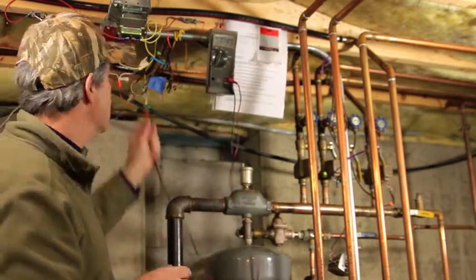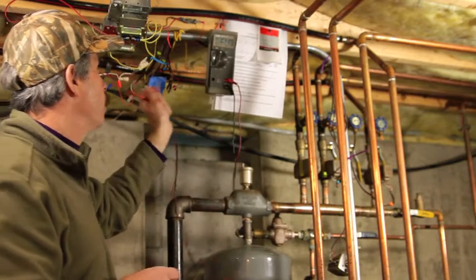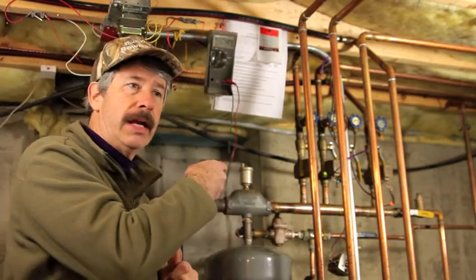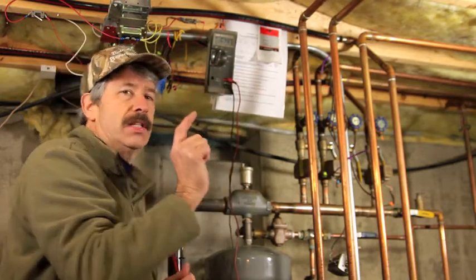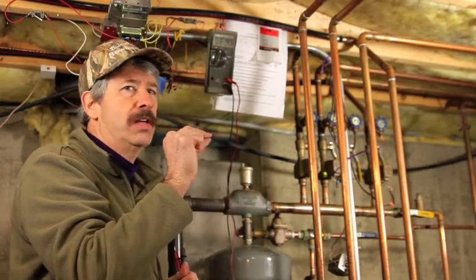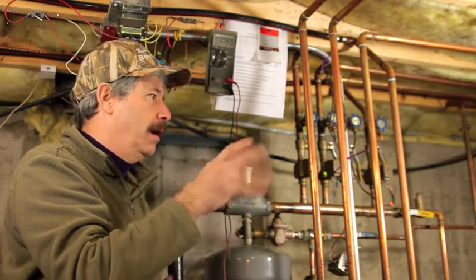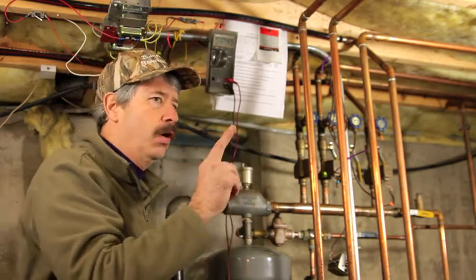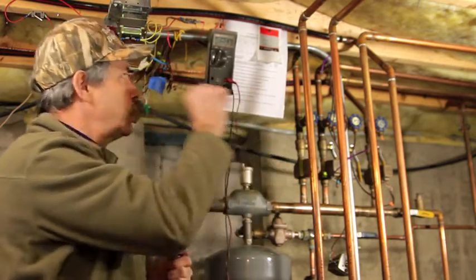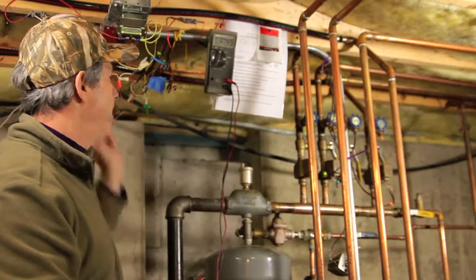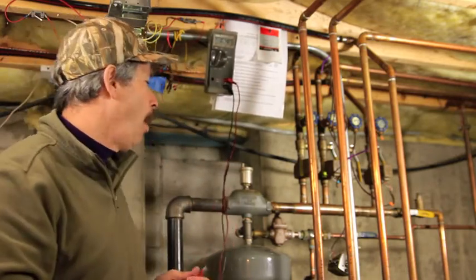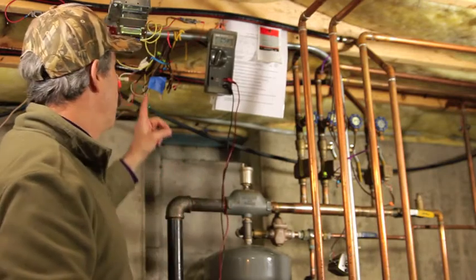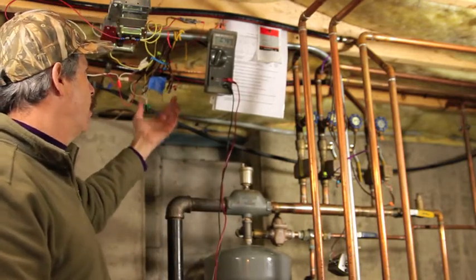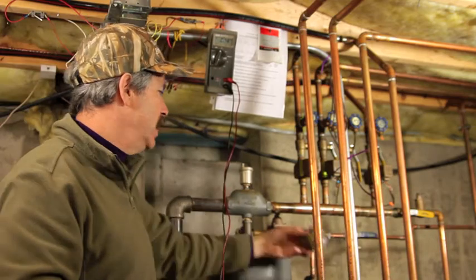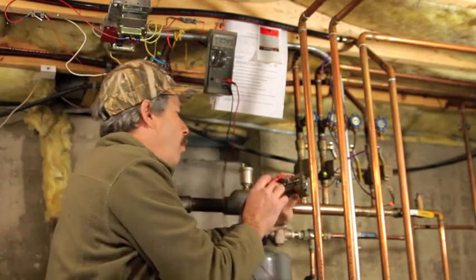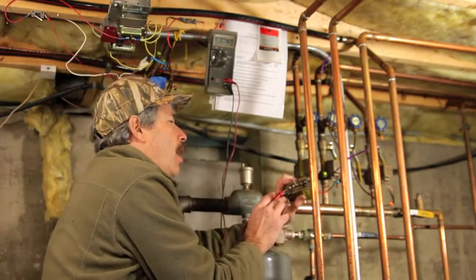Now, what happens is from the transformer, the voltage goes out on the red line to the thermostat. Thermostat is an open and closed switch. We don't have fancy thermostats here. We have a mercury and the rest are digital, but it's an open and closed switch. Once that switch closes, it sends a signal back, and it should be coming in on the white wire back, but whoever wired this switched it around.